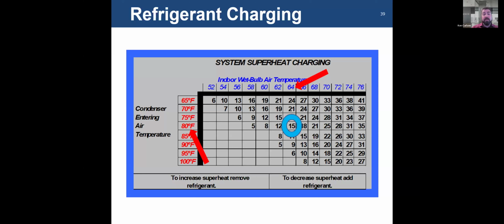for that given condition. So if your indoor wet bulb was 64 and your ambient outdoor air was 80, your superheat would be 15, right? So if your indoor conditions were higher, but your ambient conditions are still 80 degrees, you could see 18 or 21. So if you're within 3 degrees of that 15, you're probably pretty close. You can try to dial in a little bit. Sometimes it floats around a little bit, needles move. So close to 15, you're good, but get it as close as possible.